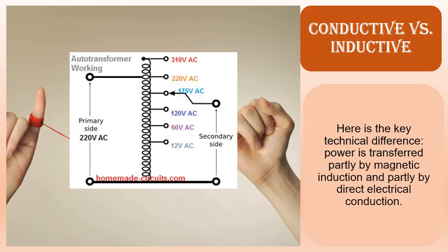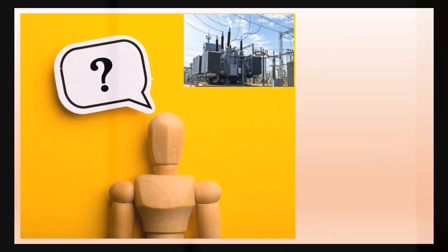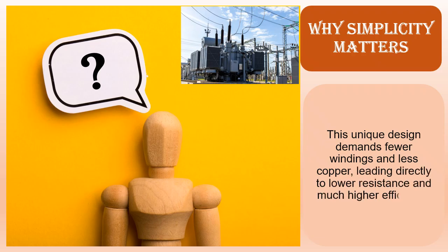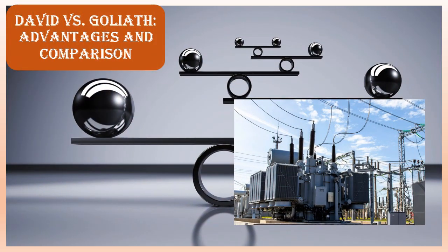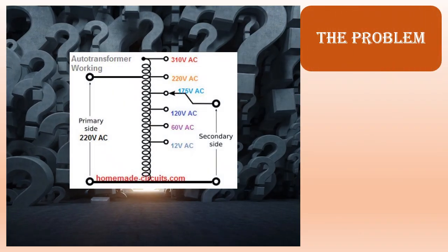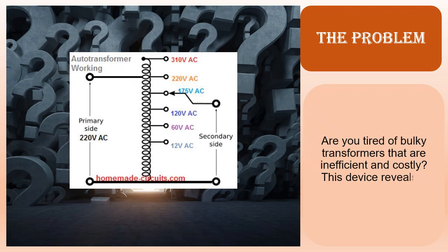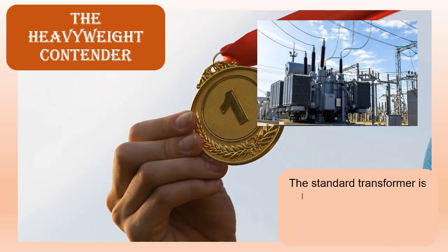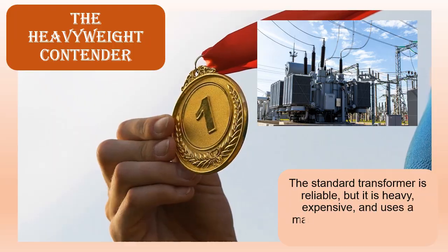The problem. Are you tired of bulky transformers that are inefficient and costly? This device reveals a surprising solution. The heavyweight contender. The standard transformer is reliable, but it is heavy, expensive, and uses a massive amount of copper wire. Copper savings. Because the autotransformer shares a common winding, it requires significantly less copper to handle the same kVA rating. The weight factor. For an electrician, weight matters.